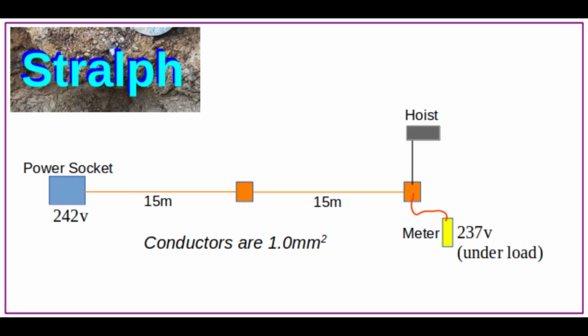That's interesting information. Hoist in the top right corner, the grey box, and the meter, little yellow box, which measured 237 volts when the hoist was working, which means there's a 5 volt drop when the hoist is working compared to when there's no load at all. And that's effectively what we did.